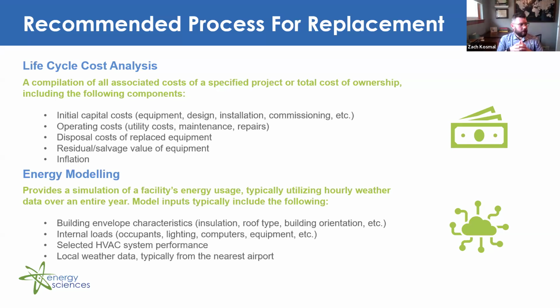And lastly, energy modeling provides a simulation of a facility's energy usage, typically utilizing hourly weather data over an entire year. This model input typically includes the following: your building envelope characteristics, internal loads, HVAC system performance, and local weather data. Energy modeling feeds accurate performance data into the life cycle cost analysis software, and this ensures that financial decisions are based on realistic energy use projections. This integrated approach is especially important for heat pump systems, where you can have significant variance in climate, load profiles, and system design.